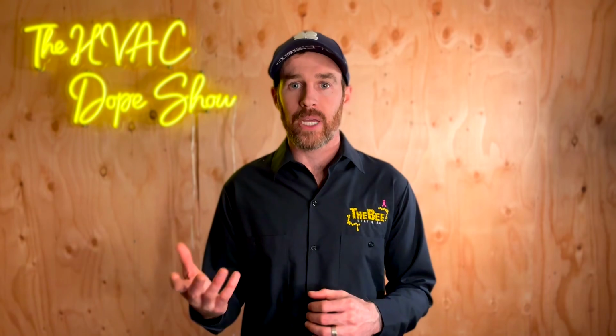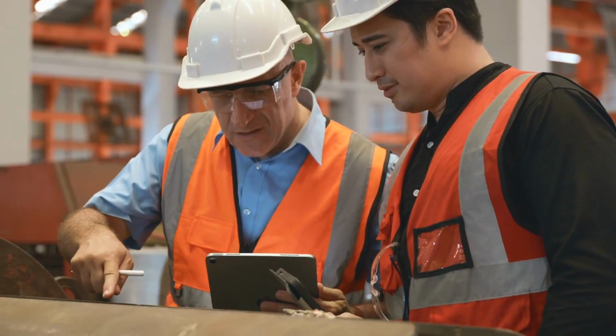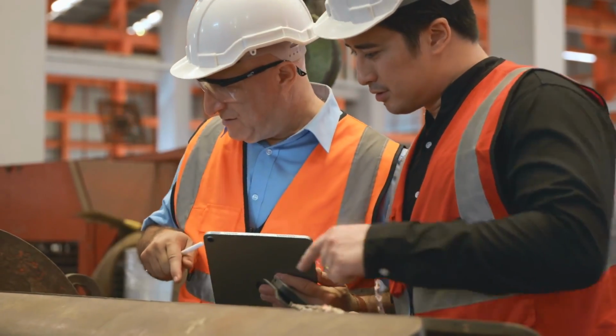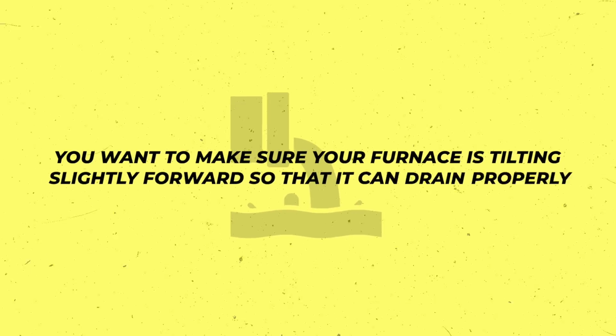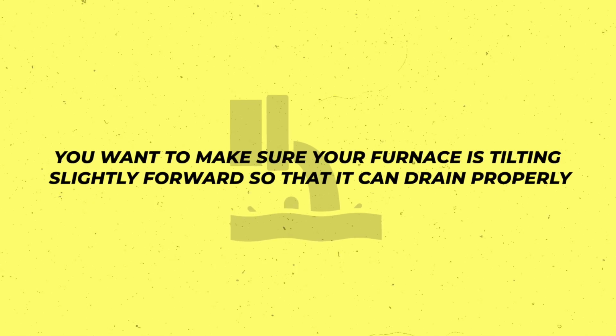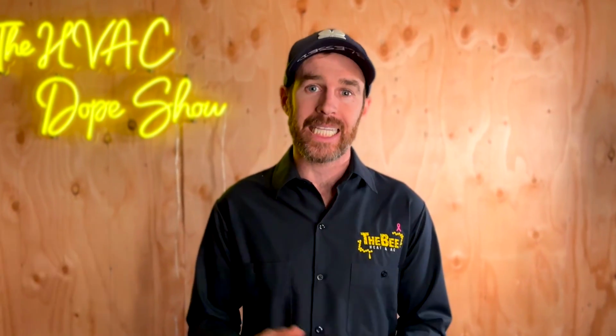And this next installation error is a gotcha that is so minor and easy to miss that oftentimes we have new technicians at our company that will miss this on their first high efficiency install. And this is why we train all our guys to look for this, because it will cause so many problems and be difficult to spot. And that is that you want to make sure your furnace is tilting slightly forward so that it can drain properly. Now, the furnace itself should have a little bit of slope tilting towards the front of the furnace because you want the condensation in the secondary heat exchanger to drain effectively out of the system.